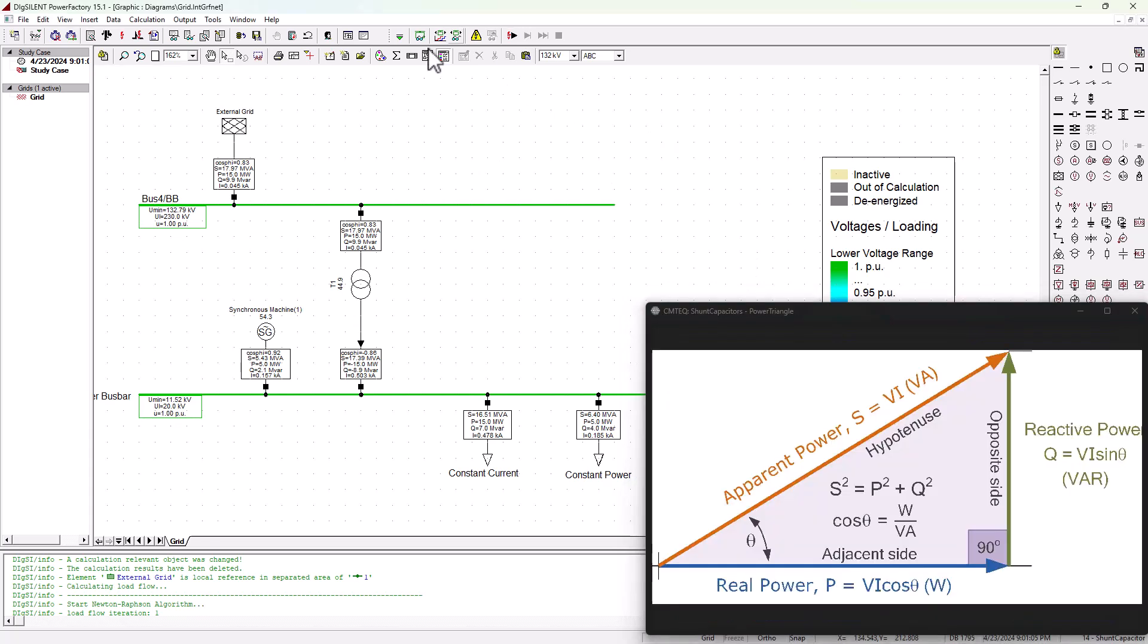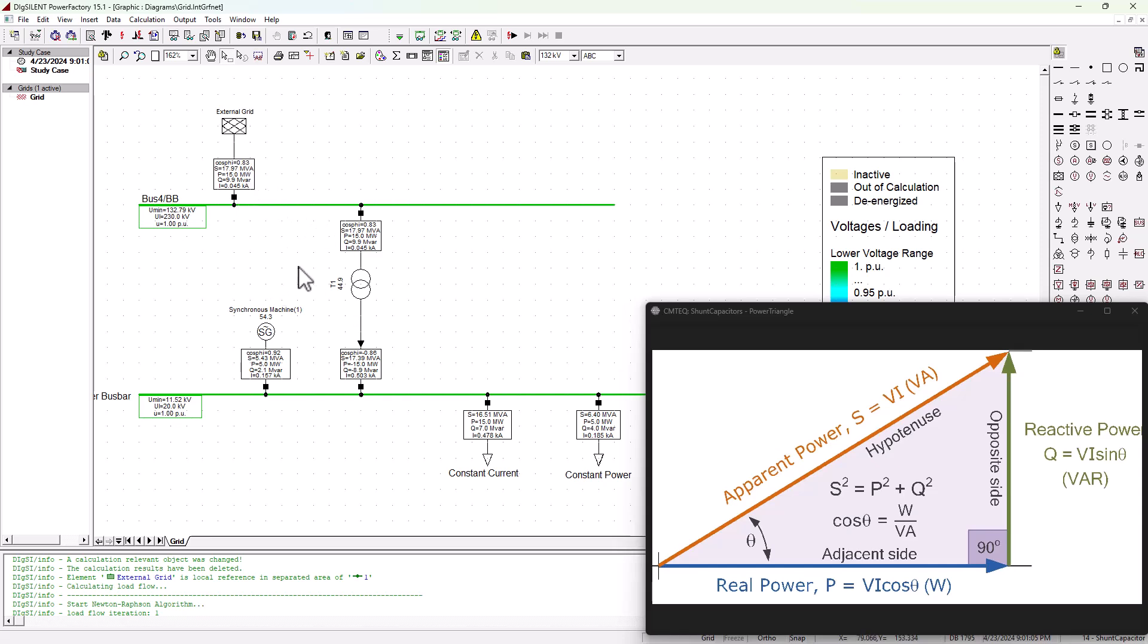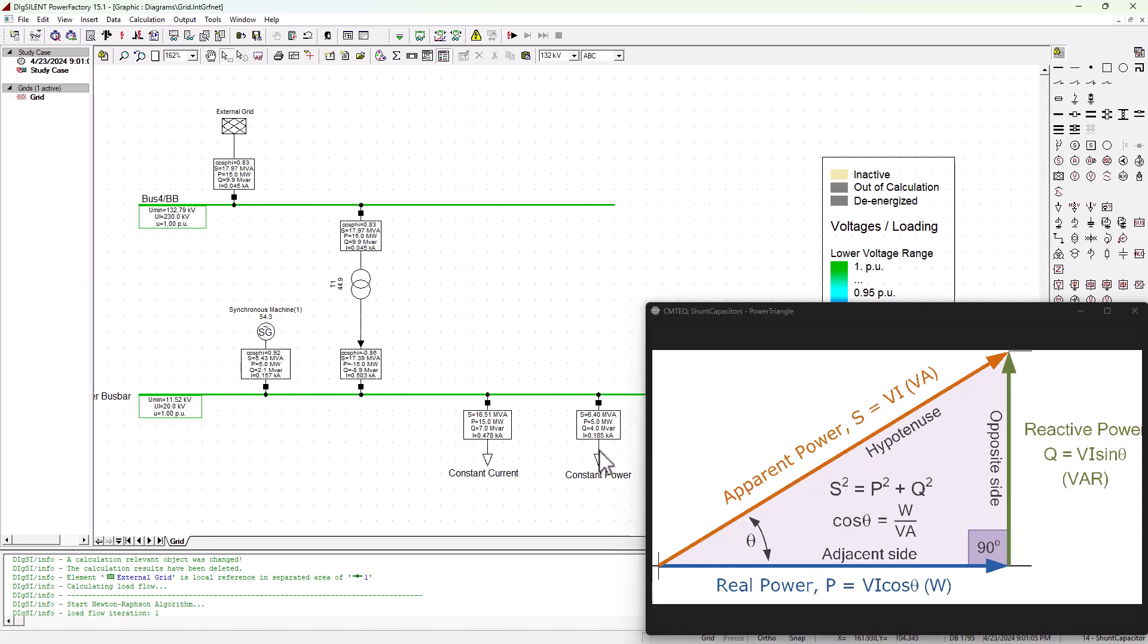Now, first things first, we need to understand the problem statement before moving forward. We know that the external grid is supporting our network with 9.9 MVAR, and that is resulting with a 0.83 power factor. Here on our network, we also have a synchronous machine that is contributing 2.1, and as we can see, our two loads combined are absorbing about 11 MVAR.